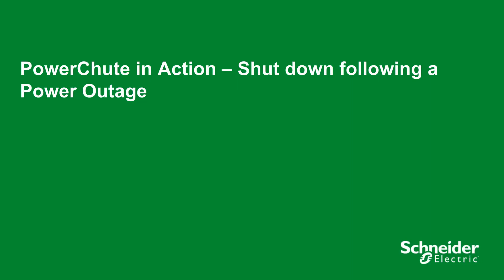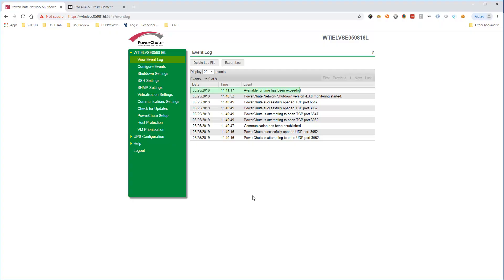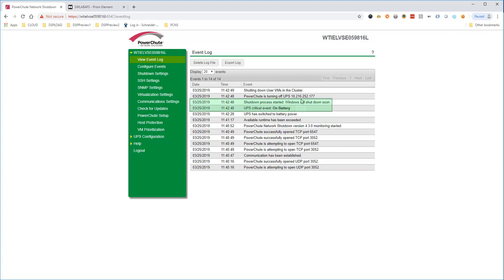We will trigger a power outage on the UPS protecting the Nutanix block to illustrate the shutdown sequence. For the purposes of the demo, we have set a short delay for the on-battery shutdown action. PowerChute detects the UPS running on battery power, and after the configured delay, the shutdown sequence starts. User VMs are shut down first.